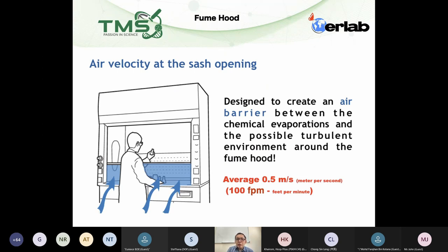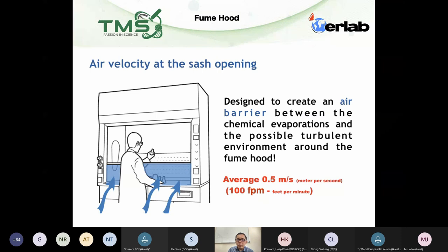When we open a container of chemicals inside a fume hood, we make sure the face velocity at the opening is 0.5 meters per second and above. If you convert that to feet per minute, it will be 100 feet per minute — that is the minimum requirement.